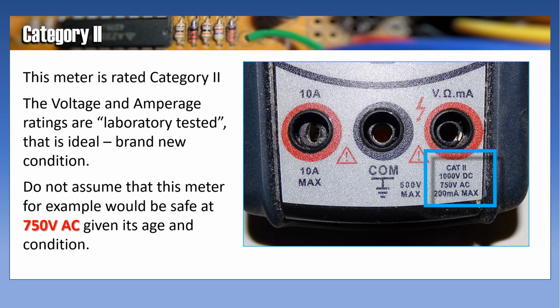When looking at a meter and checking its category, you have to use some common sense. This meter shown is rated a Category 2. Now the voltage and amperage ratings are laboratory tested, that is, in ideal brand new condition. Do not assume that this meter, for example, would be safe at 750 volts AC, given its age and condition.